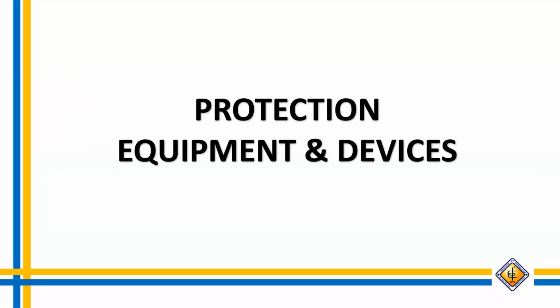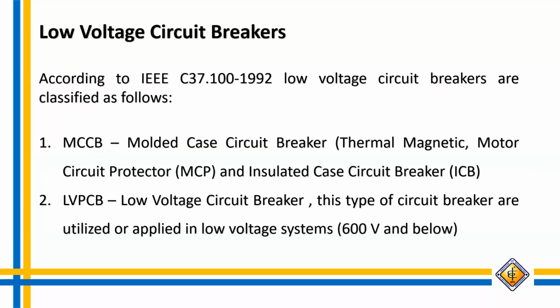So protection equipment and devices. Low voltage circuit breakers according to IEEE C37.100-1992 are classified as follows. We have MCCB and the low voltage power circuit breakers. MCCB has different types: the thermal magnetic, the MCP or the motor circuit protector, and the insulated case circuit breaker. These circuit breakers are applied in low voltage systems, which is 600 volts and below.